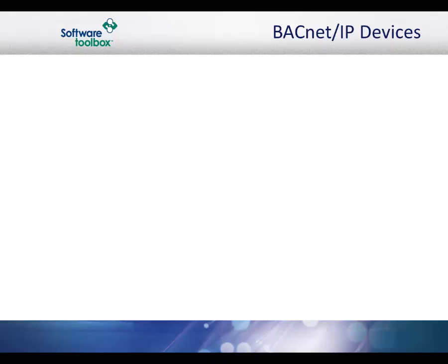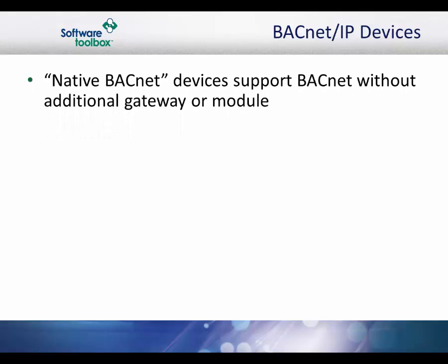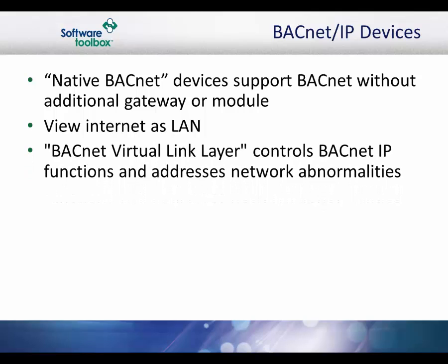The development of BACnet IP provided not only the specification for moving BACnet messages between IP devices, but also the base for accepting other new networking technologies with minimal impact on existing BACnet technology. If a device supports the protocol without the addition of a gateway or other module, it is called a native BACnet device. BACnet IP devices view the internet as if it were a local area network. The IP address of a device serves the same purpose as the device's MAC or physical LAN address in other BACnet networks. The protocol uses a BACnet Virtual Link layer to control all of the BACnet IP functions. This layer provides a string of messages that are used to address specific abnormalities of IP networks, including the behavior of broadcasts.